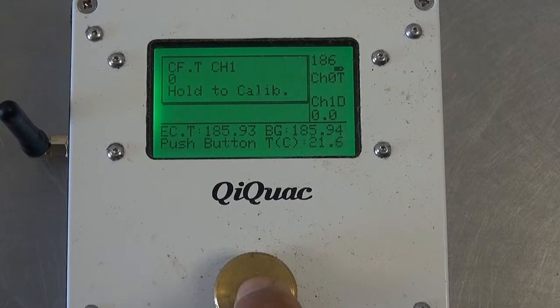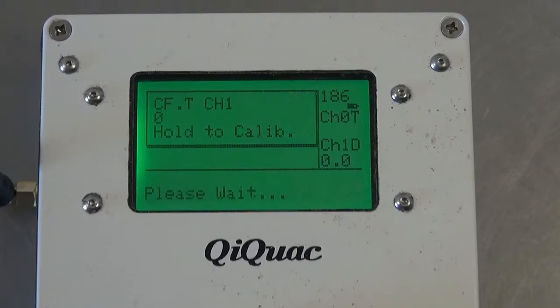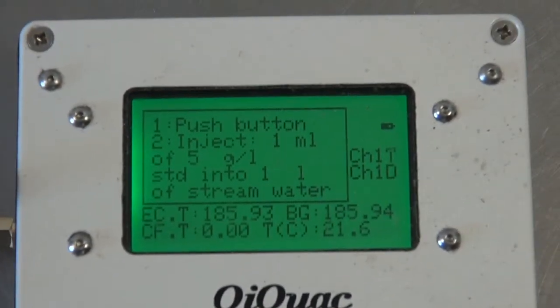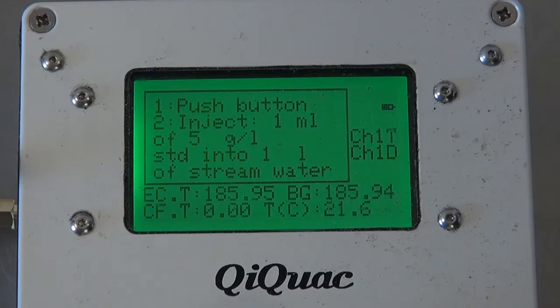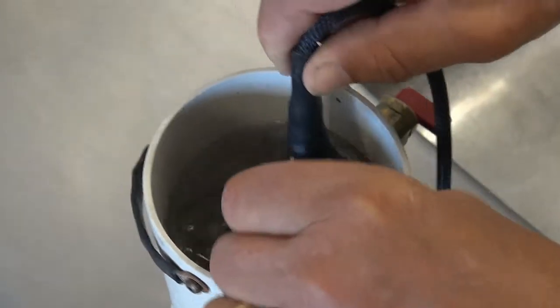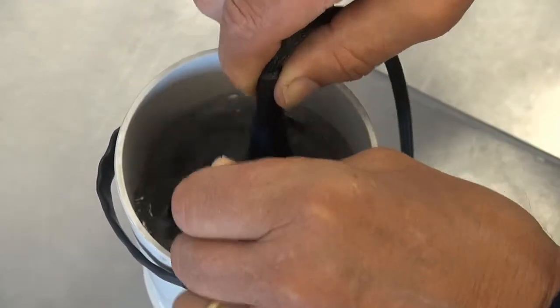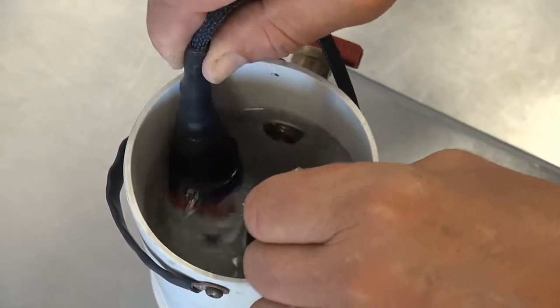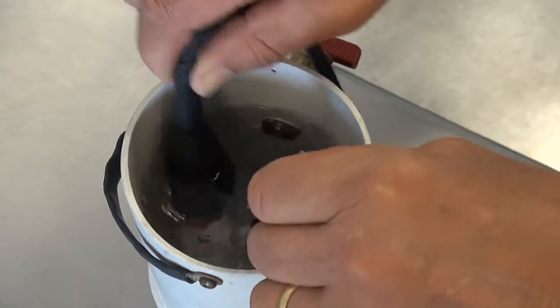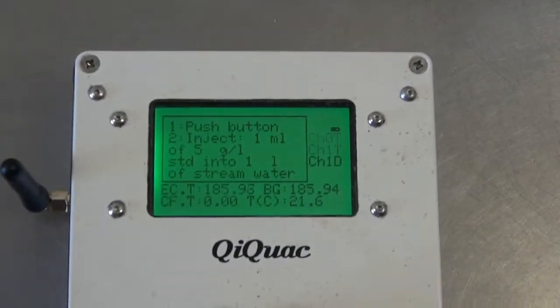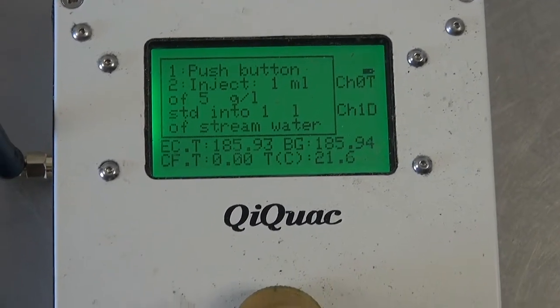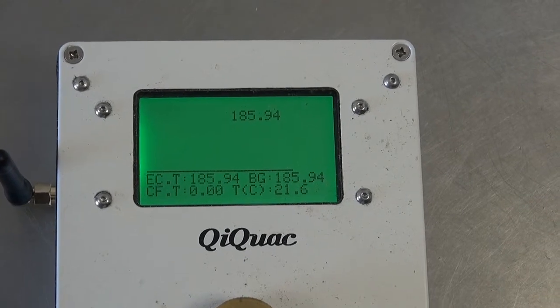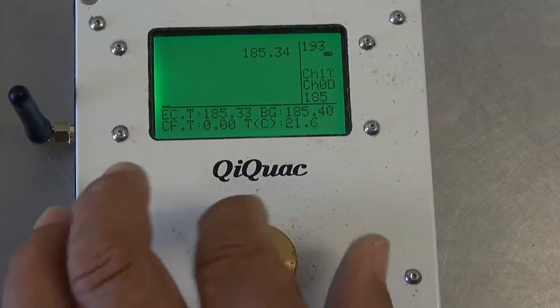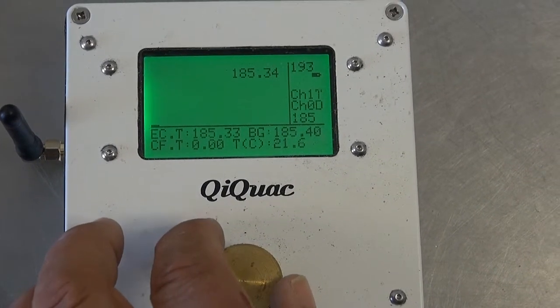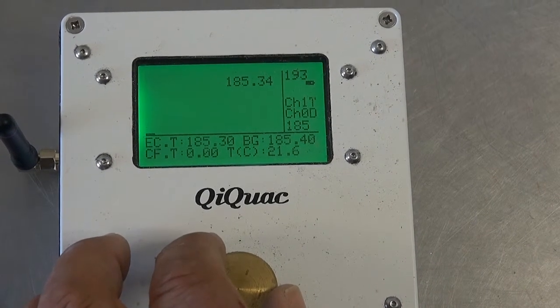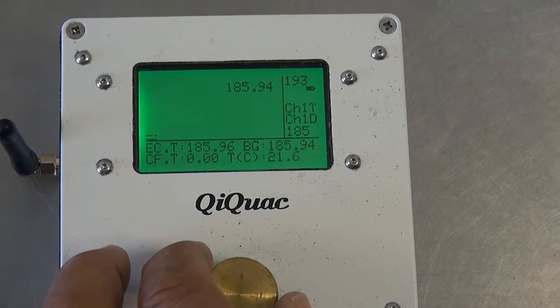We want to go into the calibrate, so we're now just holding it to calibrate. Let it go. And it's waiting. It's getting its own readings now. We make sure we jiggle the probes, make sure there's no air trapped in them. Swirl it around a bit, make sure it's complete. This is the background solution, so we shouldn't need any mixing because there's nothing added into it. We just leave it there like that. Then we push the button again, and here are our first readings. I'm just turning that back 1 toggle at a time. So that's 1 probe, 185.34. The other probe, 185.94.